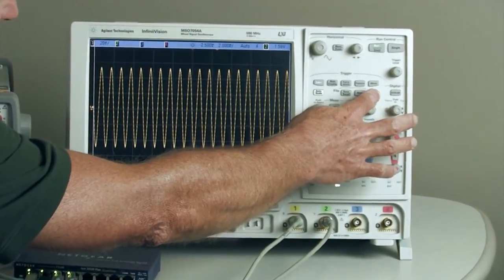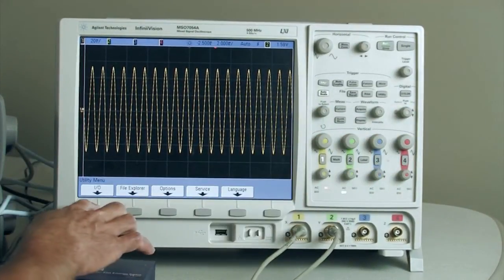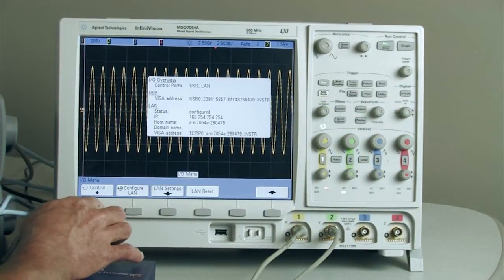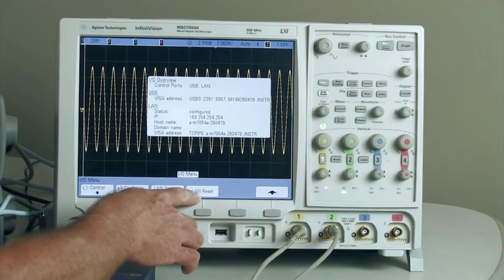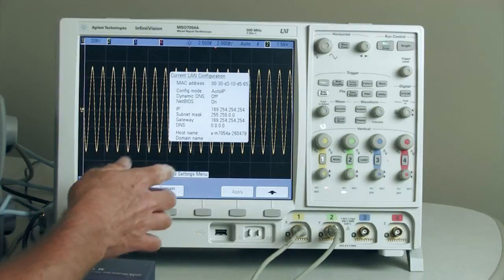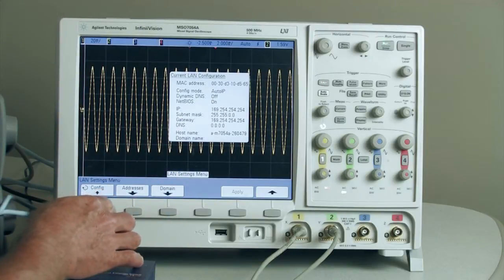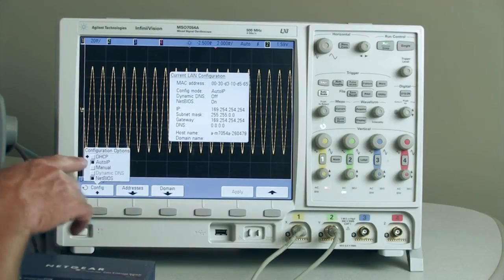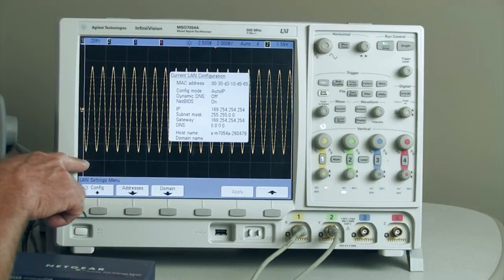All the instruments are basically the same. They have a utility menu. We want to pick the I.O. feature and here's the LAN reset button. On the oscilloscope, I notice it's best to actually set the oscilloscope to use the auto IP feature. So the way we do that is there's a selection between DHCP and auto IP. So I've selected the auto IP before doing our LAN reset.